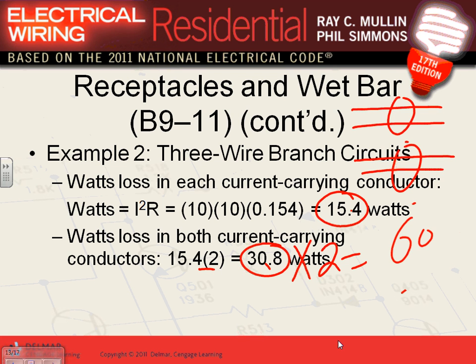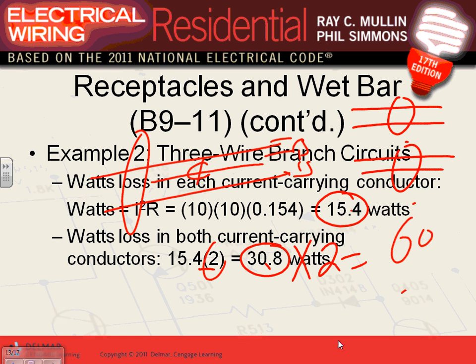Now, if it's a 3-wire multi-wire circuit, what happened to the neutral? The neutral doesn't count. All these circuits are tied together, so there are only 2 wires. That will multiply by 2. You cut the losses by half, the copper losses. Now it doesn't matter, guys, that's not a whole lot if it's one multi-wire branch circuit. Imagine the whole building is multi-wire branch circuits. That makes a big difference.